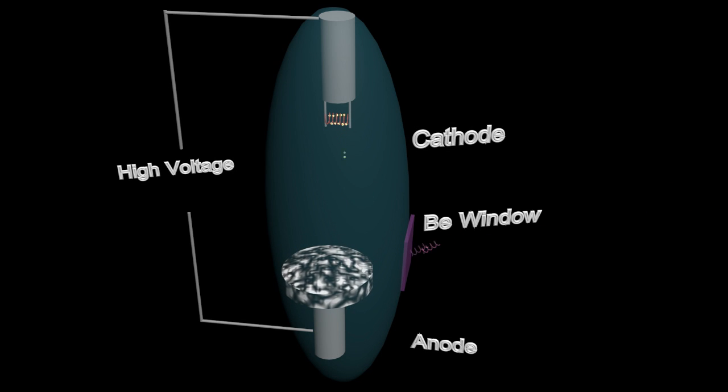Using a rotating anode allows the heat to distribute on a larger surface area, and this allows to generate x-rays with much higher energies and intensities.